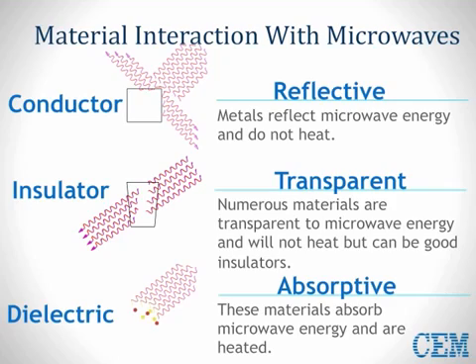Dielectric materials will interact with and absorb microwave energy. You do not want to have these materials present in the cavity — as either part of the vessel or turntable — because these materials can change the microwave pattern and therefore create hot and cold spots in the microwave cavity, which will lead to uneven heating.